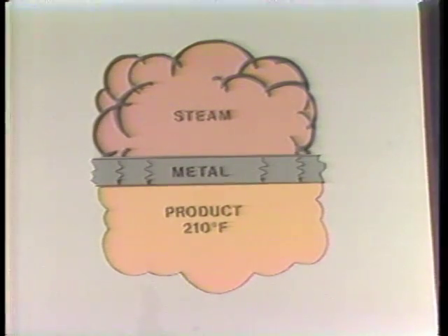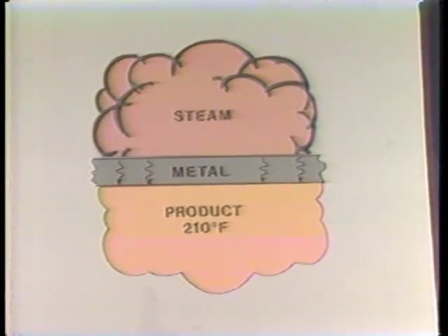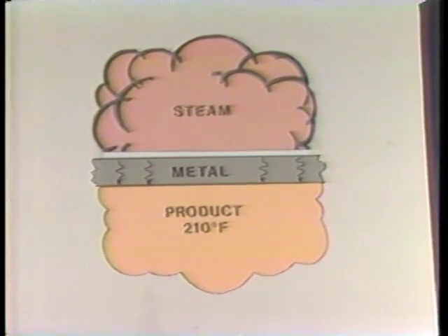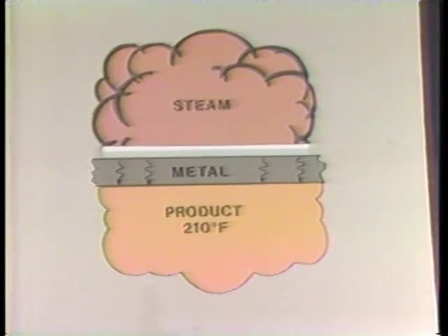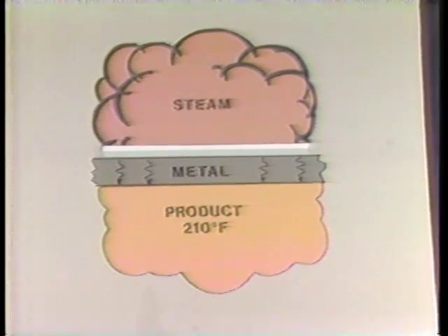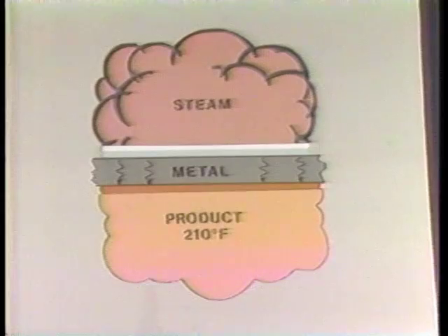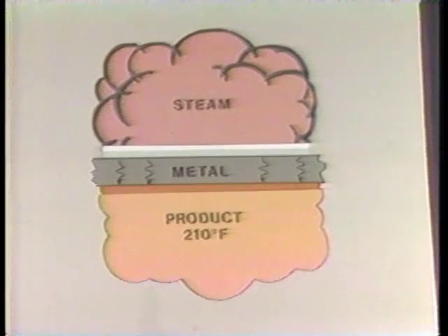This illustration shows a cross-section of the heat exchange surface for a process requiring a product temperature of 210 degrees Fahrenheit. As steam reaches the surface, it gives up its latent heat and condenses, leaving a film of condensate. Air in the steam collects with the condensate on the inside of the heat exchange surface. If the heat exchanger is immersed in the product, a layer of water or burned product may form on the outside. To overcome these heat transfer barriers and obtain a product temperature of 210 degrees Fahrenheit, the supply steam must be set at 15 pounds gauge or 250 degrees Fahrenheit — a 40-degree temperature loss from the insulating layers.